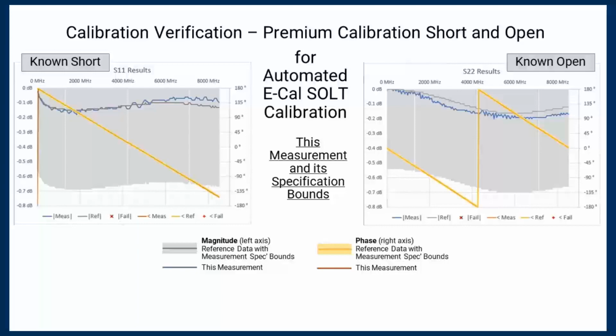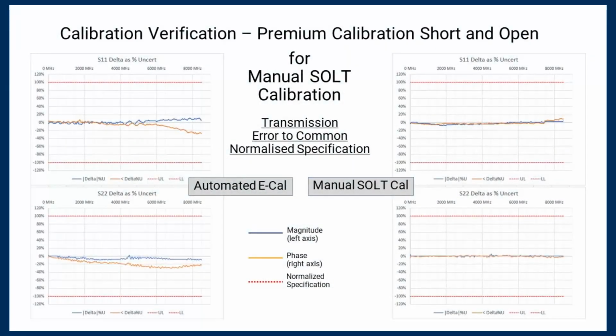Phase is also in spec because there are no red crosses on these plots, but let's look against normalized reference and spec to see how well they actually match. Well, very good match indeed. Phase as well. So again, we have eCal on the left, and on the right, manual cal is an even better match to its own reference. But both are very well within our specification, even though we used the PC 3.5 uncertainty. We can begin to wonder whether any competitor AutoCal solution would anywhere near match this.